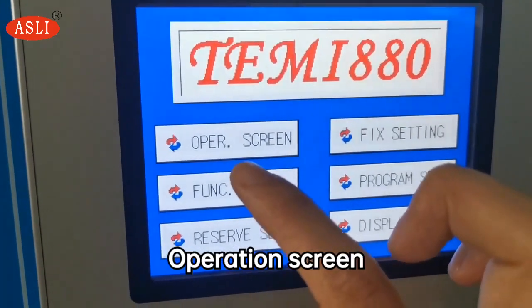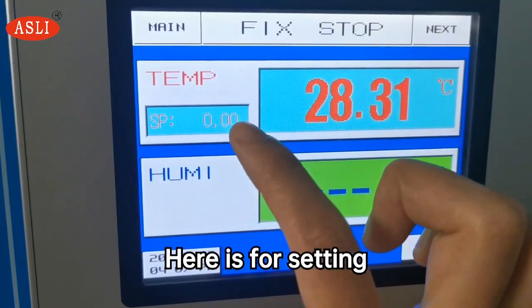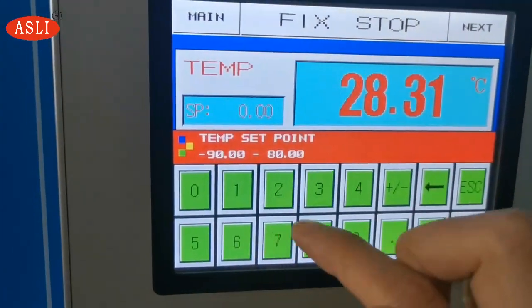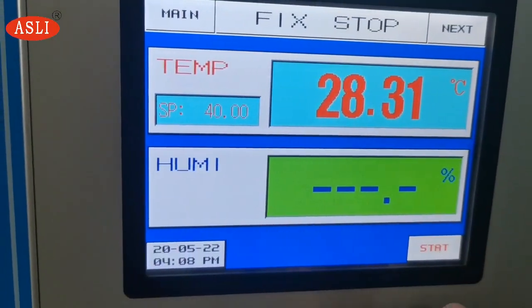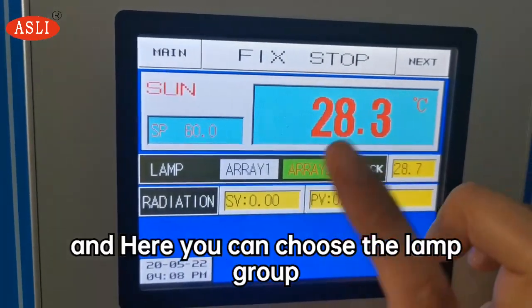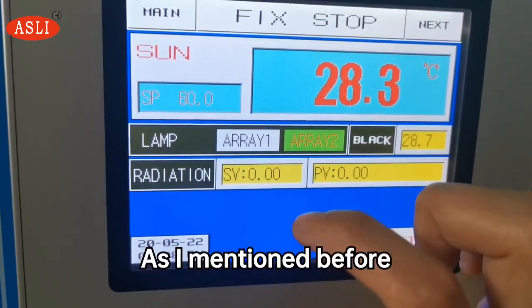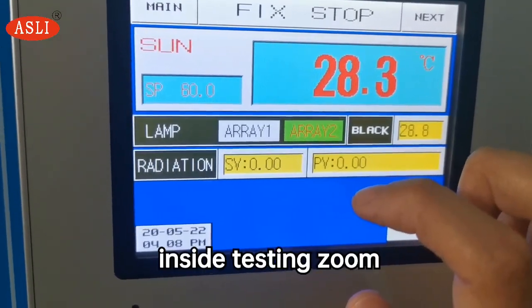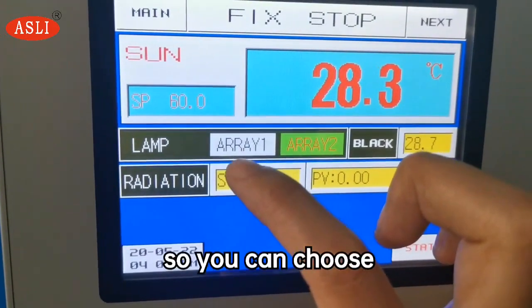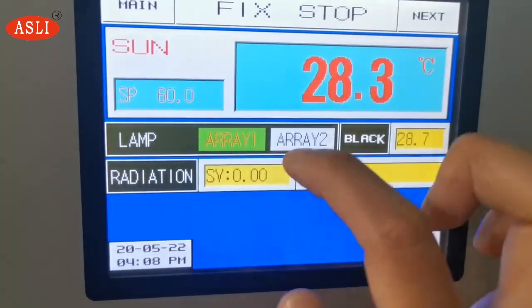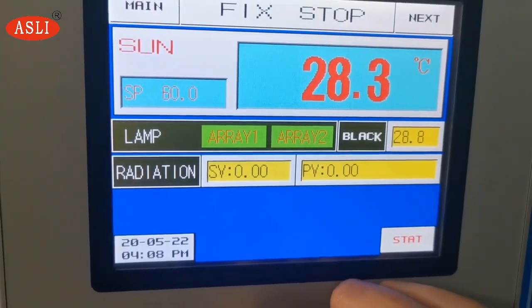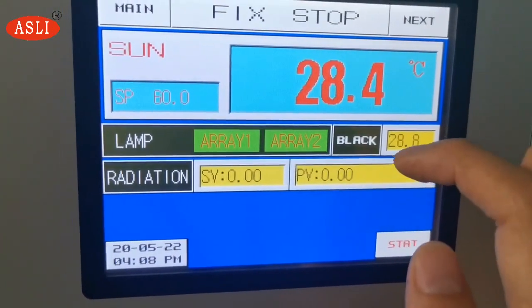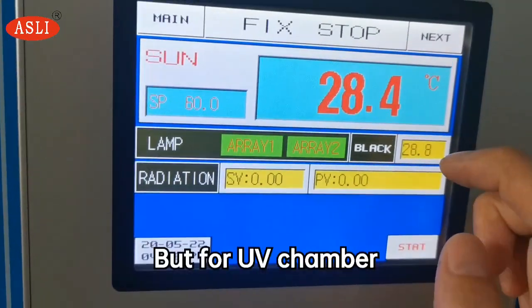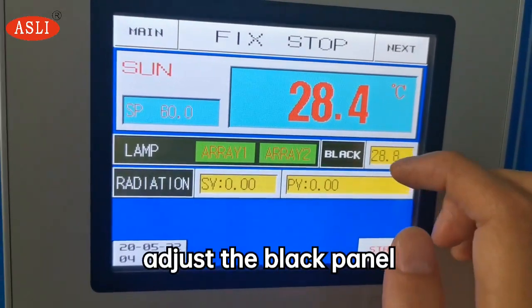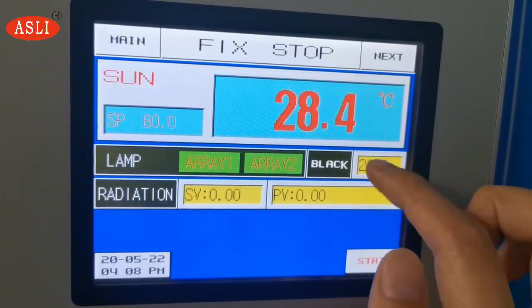After setting the program, we come here, operation screen. Here is for setting the temperature, for example, 40 degrees centigrade. And here you can choose the lamp group. As I mentioned before, there are 10 lamps inside the testing room and 5 as a group. So you can choose the first group or the second group or both. This is the black panel temperature. But for the UV chamber, we cannot adjust the black panel. It is not adjustable.